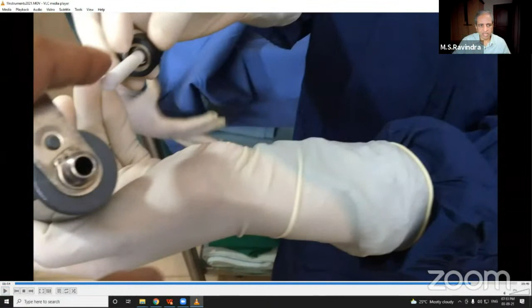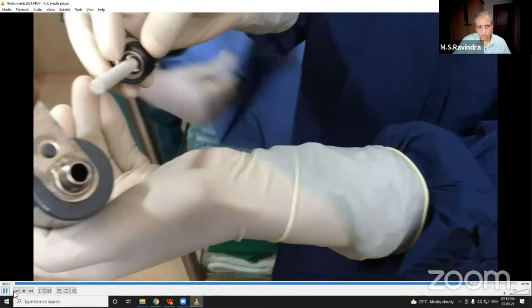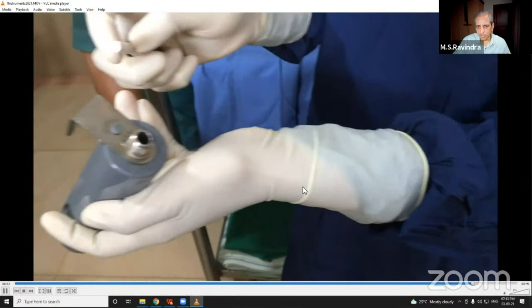The tape, there is a special signal indicator which goes inside this plastic tube, and that gets into, as you can see, he is going to screw it inside, and this has to pass. For every autoclave cycle, we have to do the test. So the first thing in the morning, the nurse is going to check whether the strip is completely black in color. It should be completely black in color, not gray in color. And then only we are going to start the surgery.